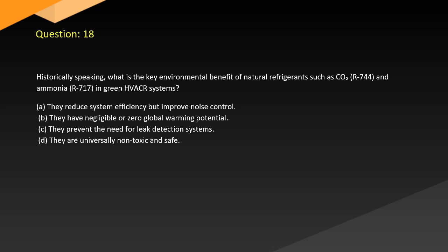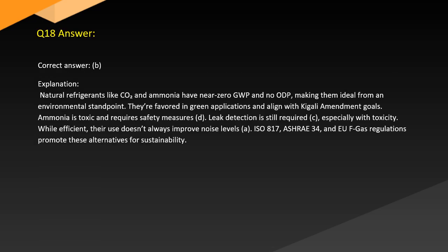Answer. Correct answer: B. Explanation. Natural refrigerants like CO2 and ammonia have negligible GWP, making them ideal from an environmental standpoint. They're favored in green applications and aligned with Kigali Amendment goals. Ammonia is toxic and requires safety measures (D). Leak detection is still required (C). While efficient, their use doesn't always improve noise levels (A). ISO 817, ASHRAE 34, and EU F-Gas regulations promote these alternatives for sustainability.